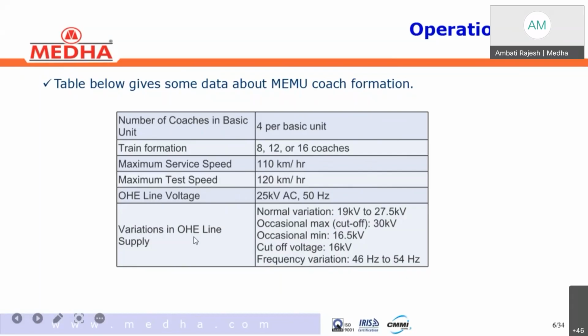And the OHE line voltage, in general the nominal supply, we'll call it 25 kV single phase 50 Hz supply. But as per the RDSO specification, the system should work between 16 kV to 30 kV, and below 16 kV or above that, it should cut off to provide safety to the entire equipment, right? That is about OHE variations, and from the frequency point of view, it is 50 plus or minus 4 Hz. So from 46 to 54 Hz, the system can work normally as per RDSO specification.